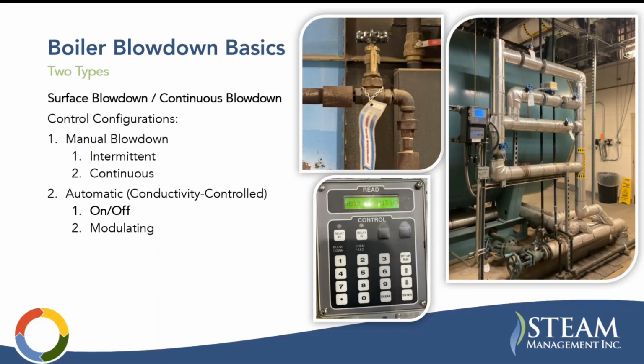Automatically controlled blowdown is what you're going to see most of the time nowadays, especially on newer systems. That's going to look something like this, where you have an actuated valve, whether that's an on-off valve or a modulating valve. You're going to have a conductivity probe measuring the conductivity, and a controller that is actuating the valve. Regardless of the control configuration, the solids accumulating inside the boiler dictate the blowdown amount required. So the calculations that we'll go through later will be a good estimate of blowdown regardless, and then it's just how close are they controlling the blowdown to what is actually needed.